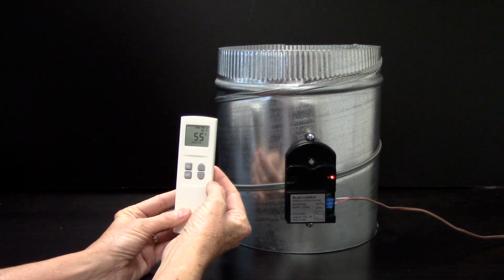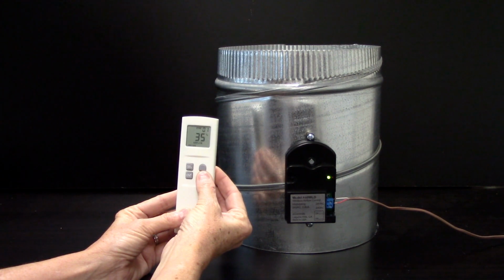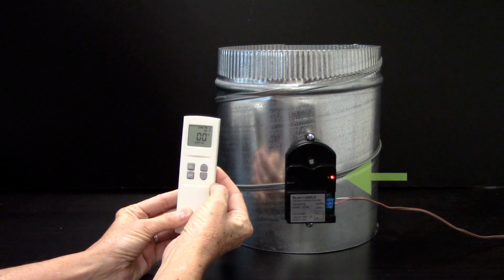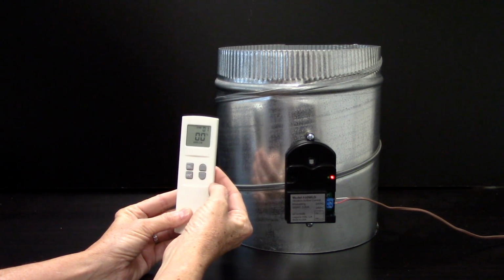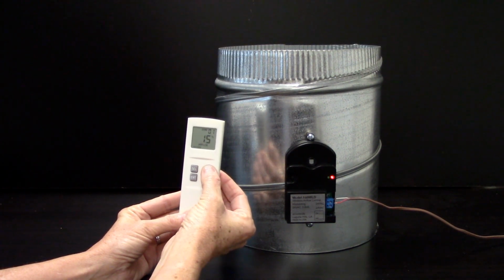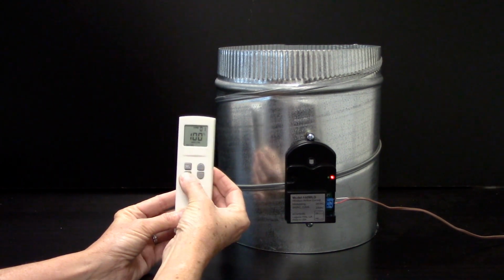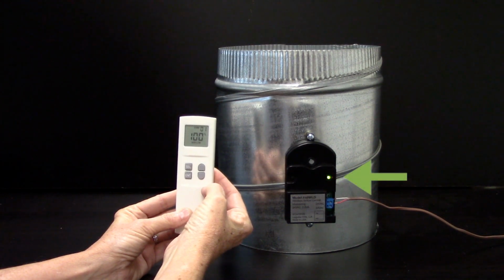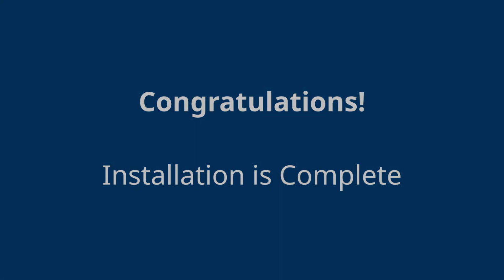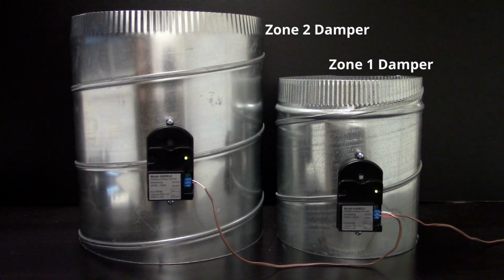partially closed position. Press the down key until 0% is displayed, then press Enter. All dampers should be displaying a red LED, indicating the damper is in a closed position. Let's return the dampers to the open position by pressing the Up key until 100% is displayed, then press Enter. All dampers should be displaying a green LED. If you don't need to set zone numbers, congratulations! Your installation is complete. Now let's take a look at controlling multiple spaces and setting zone numbers.